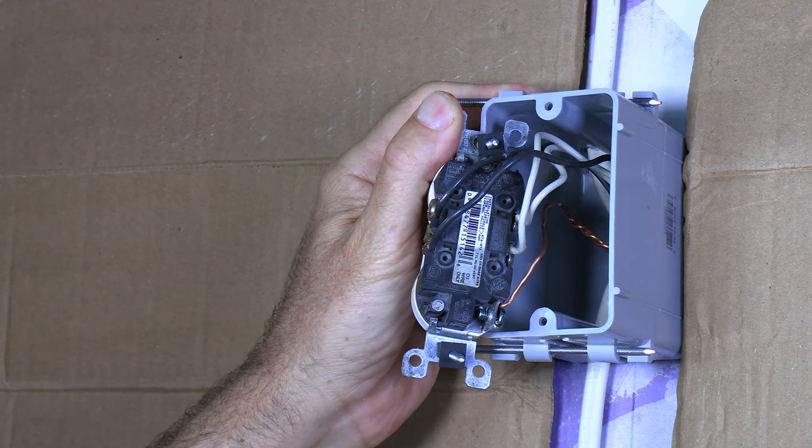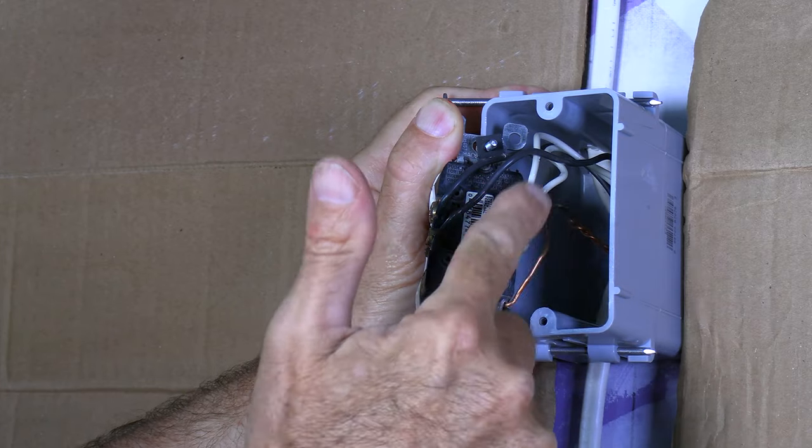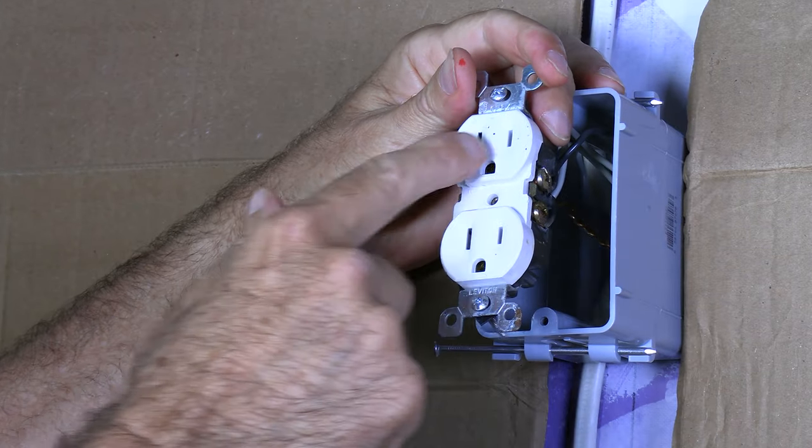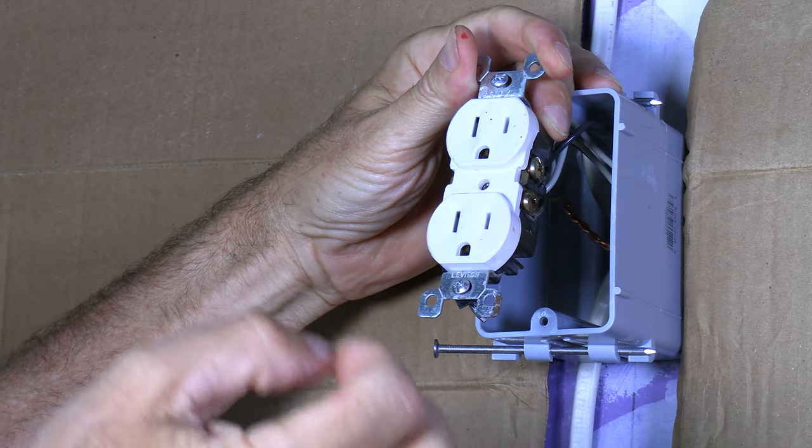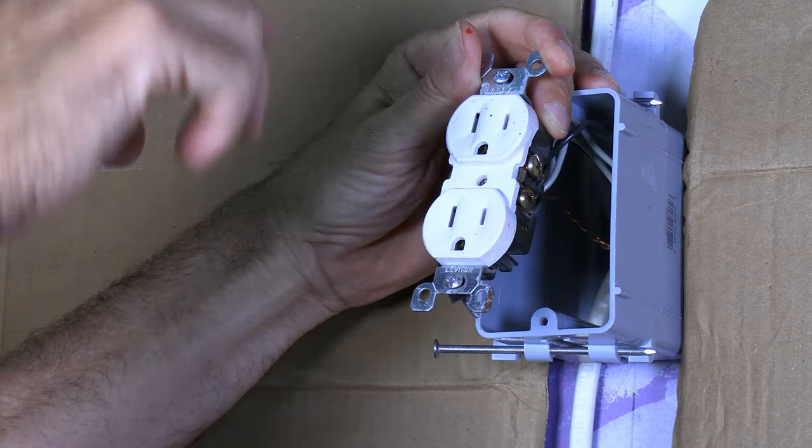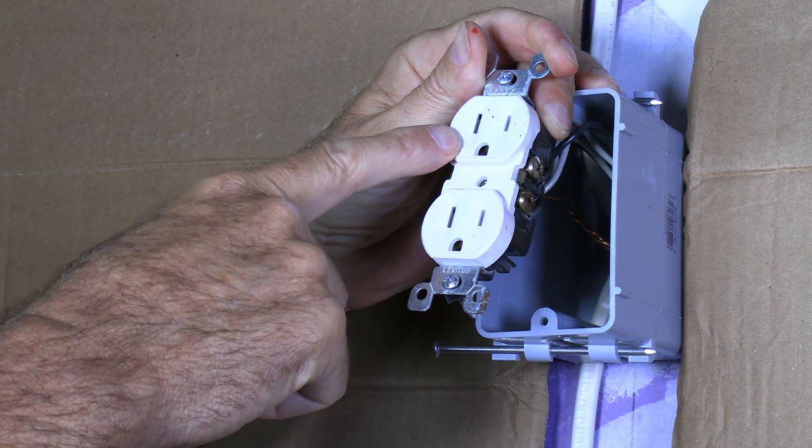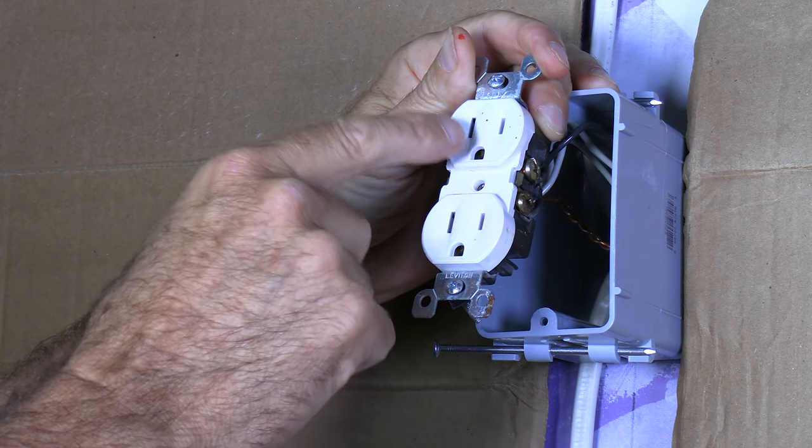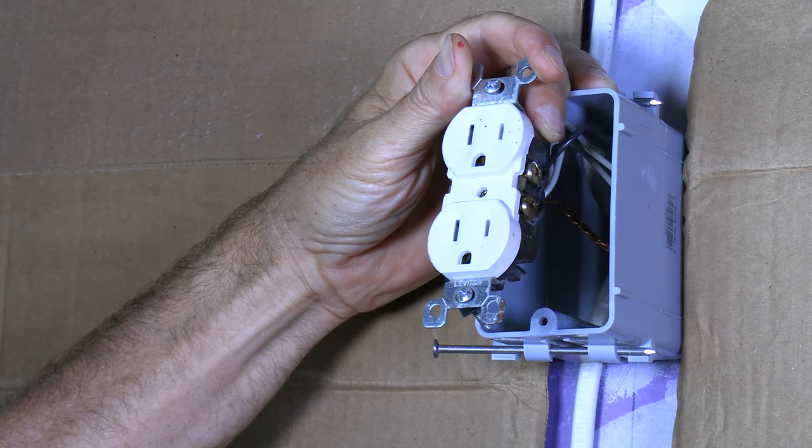One other thing I wanted to kind of re-emphasize is don't make the mistake of mixing up your hot wire and your neutral wire, like put the white over here and the black over here. Because what will happen is now this larger prong will become hot and this one will become neutral. And normally it'll work and you'll never notice the difference. But you know what can happen? If somebody takes a lamp, for example, and was changing the bulb, well, the threads around the light bulb are your neutral. But if this is reversed, now that becomes hot and somebody can touch that silver part of the lamp thread and shock themselves right there. So you want to make sure you get that right.